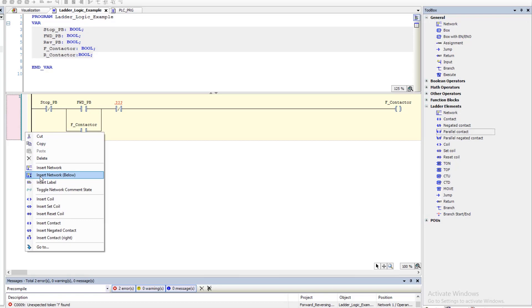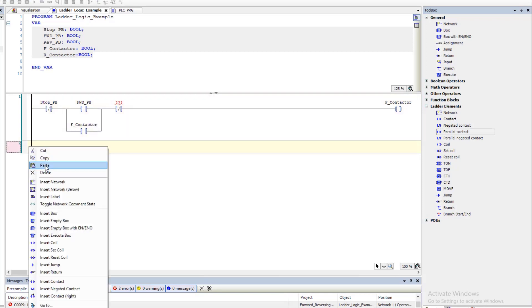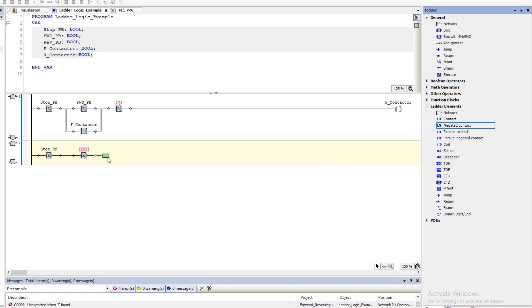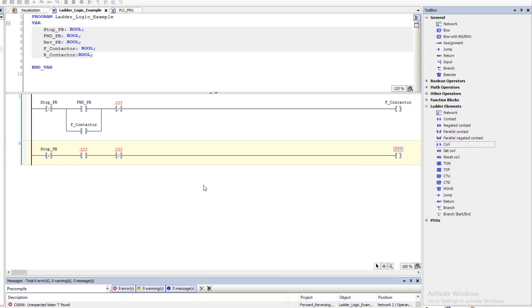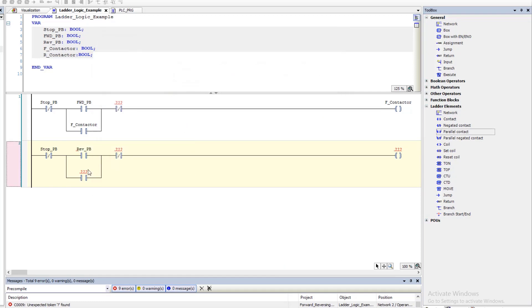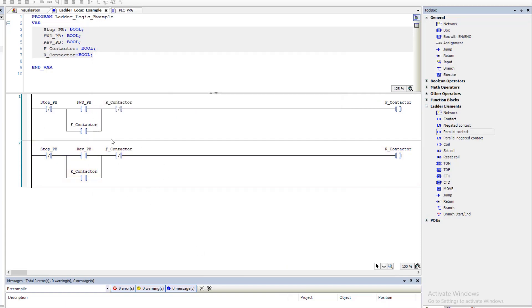Now I'm going to insert a network below and do the same exact thing for the reversing rung. We'll use the stop button again, add the negated contact, a coil, and a parallel circuit for the seal-in. This will be our reverse push button, the reversing contactor, and for the interlock we're going to add the reversing contactor contact on the forward rung and the forward contactor contact on the reversing rung so they cannot work at the same time.